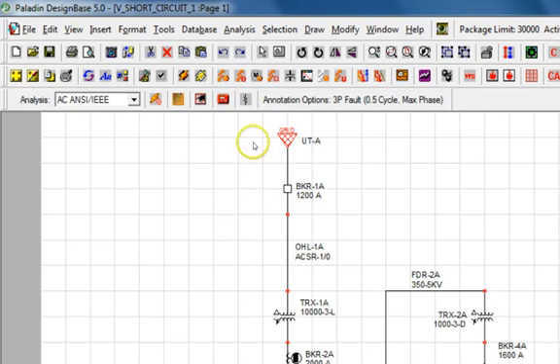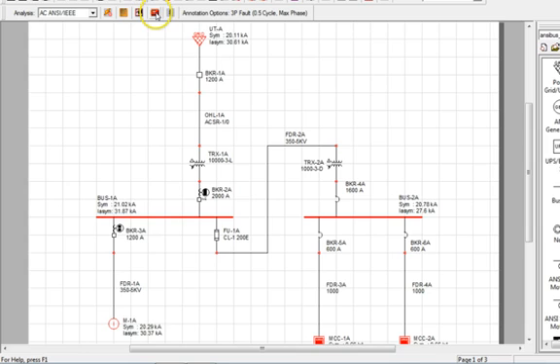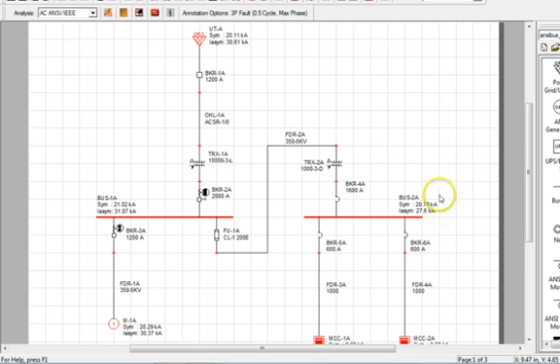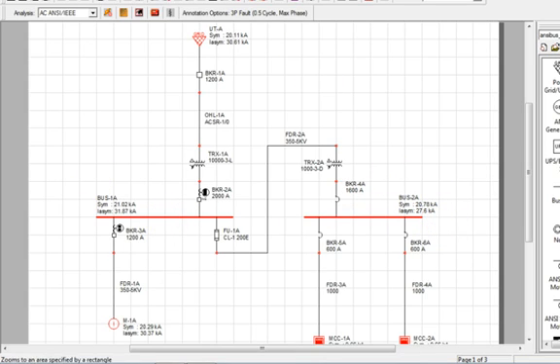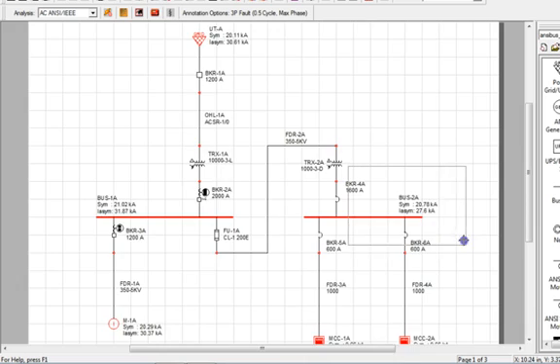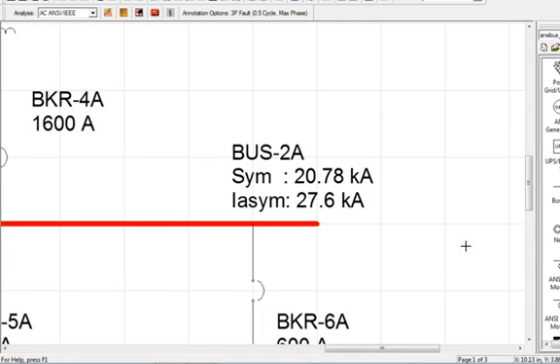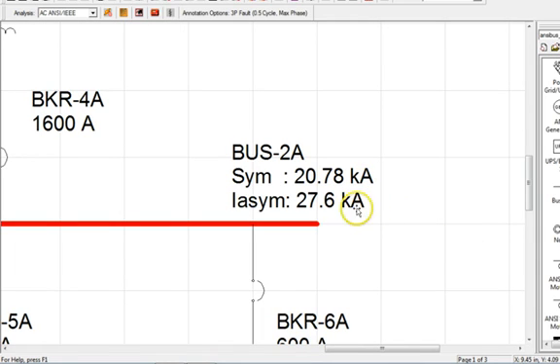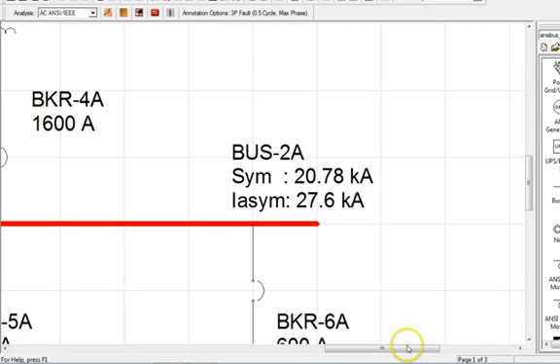The next icon is the Analyze command. Pressing this button will execute the Short Circuit Analysis. So, let's go ahead and proceed. Once the analysis is completed, the results are displayed next to each bus of the network under study. Let's zoom into bus 2A and get a better view. As per our selections, the results show the Half Cycle Symmetrical and Asymmetrical Three Phase Fault Currents in Kilo Amps.